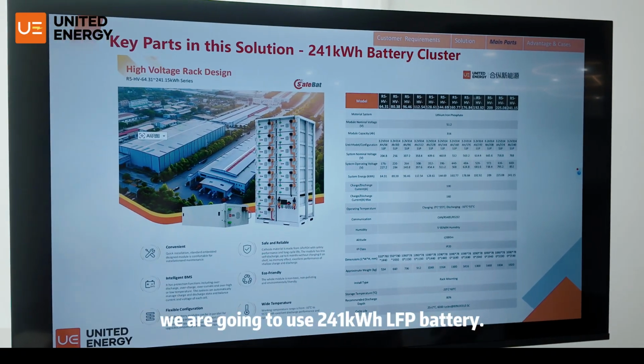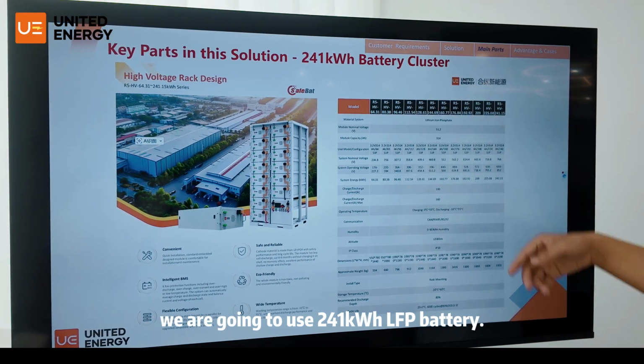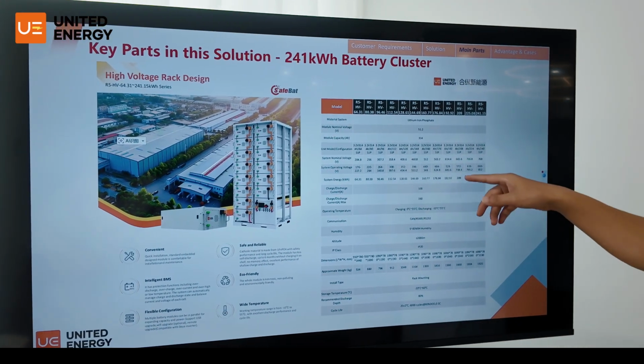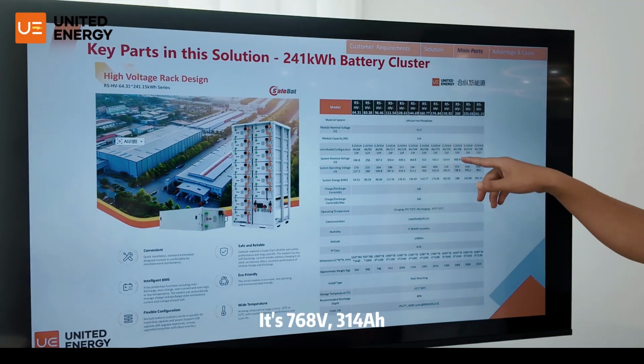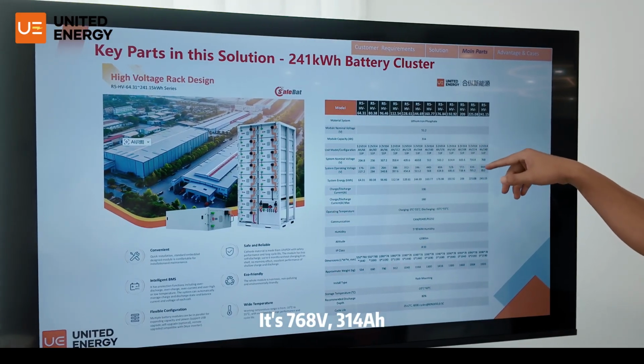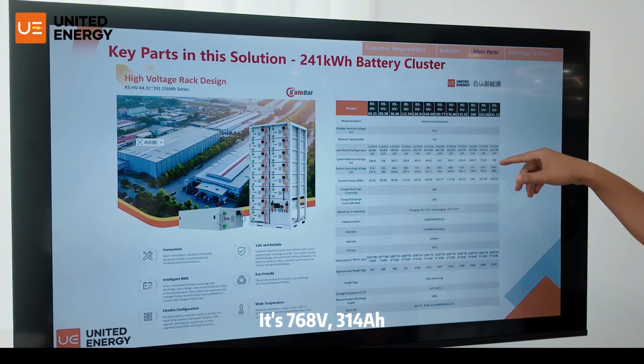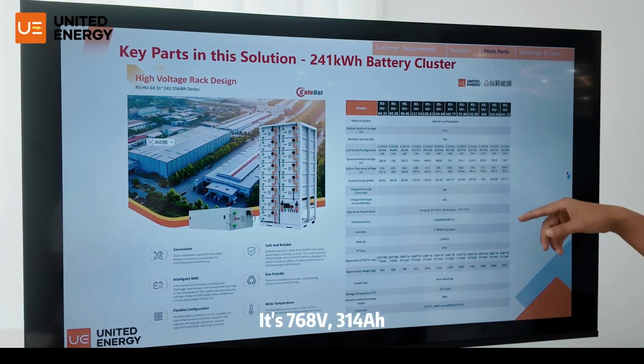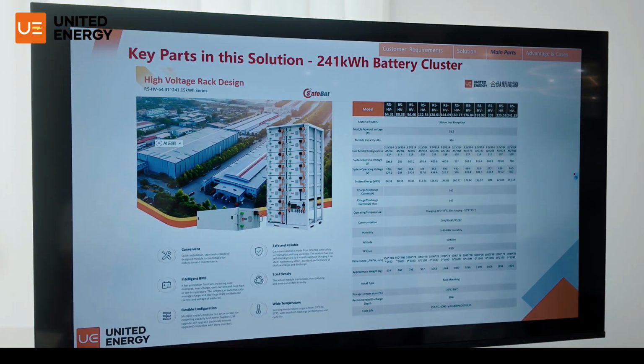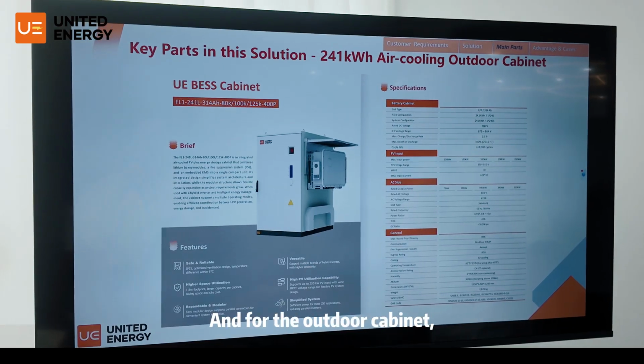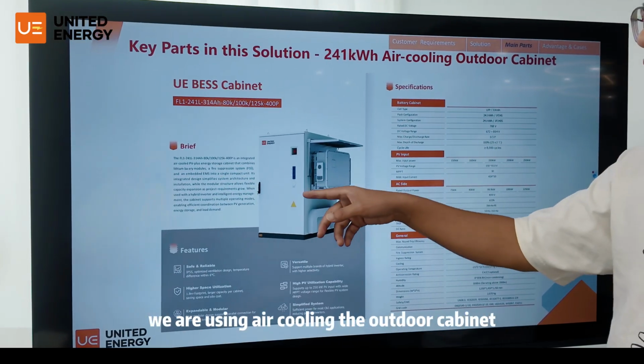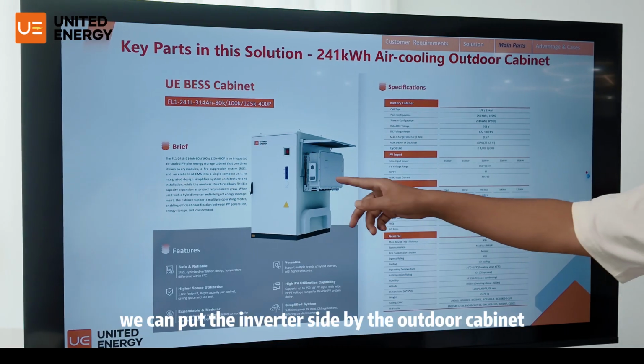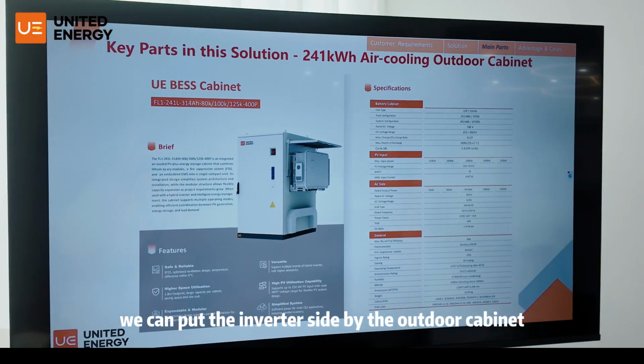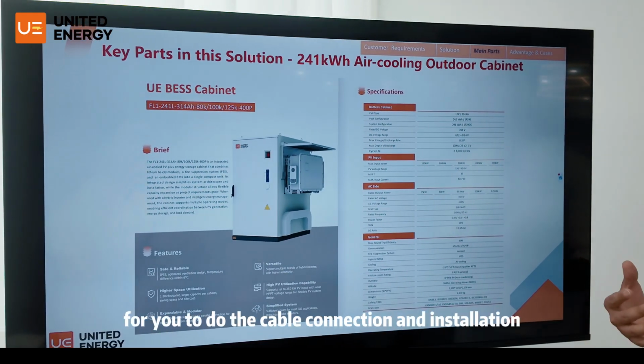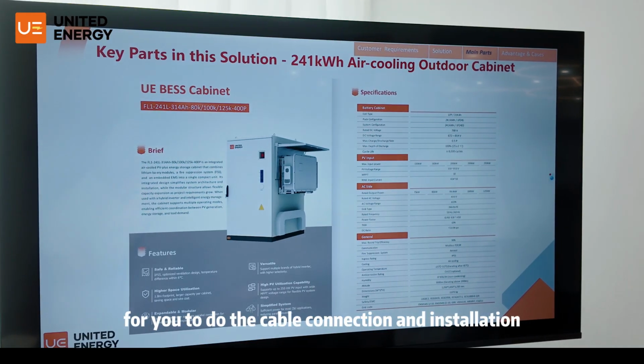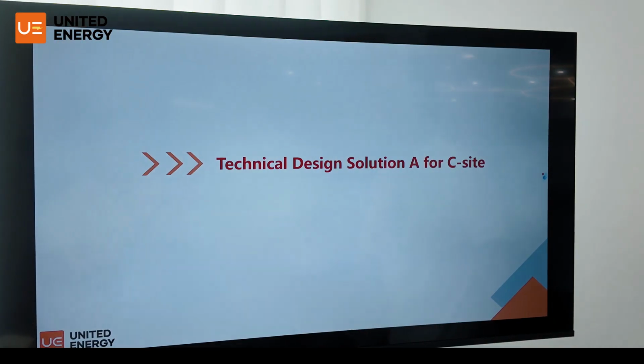And for the battery, we are going to use a 241 kilowatt hour battery, 768 volt and 314 ampere hour. For the outdoor cabinet, we are using air cooling. We can put the inverter side by side with the outdoor cabinet, and it will be easy for you to do the cable connection and the installation.